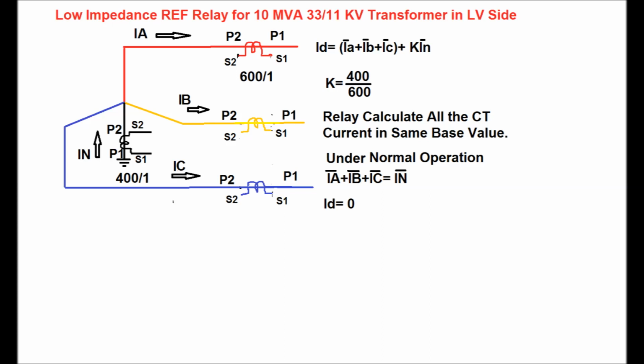So factor K is equal to NCT ratio by phase CT ratio, which comes as 400 by 600, which is 2 by 3. So we can see that the ID is calculated in the relay on the same base value, that is, in terms of the phase CT ratio. In K into IN, the secondary value of the NCT is converted to the primary value, and then it is divided by the phase CT ratio. So all the CT ratio mismatch is eliminated by the factor K.